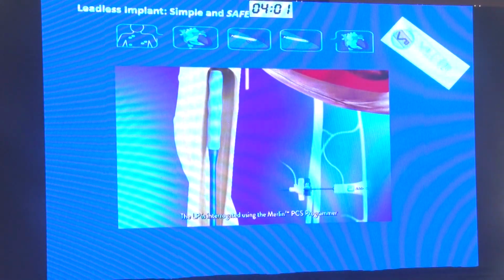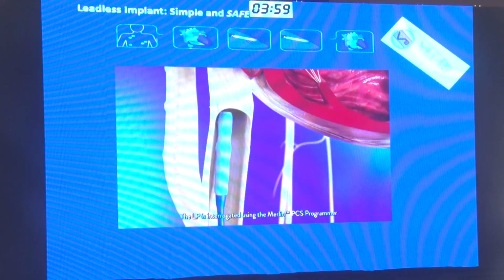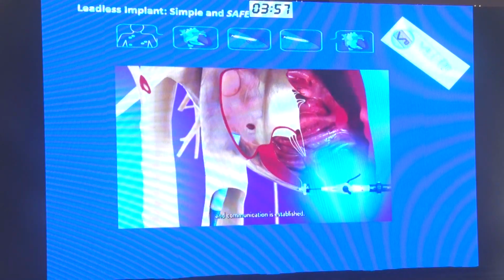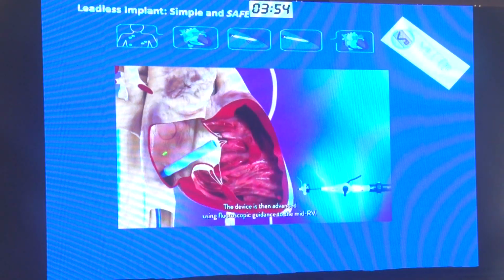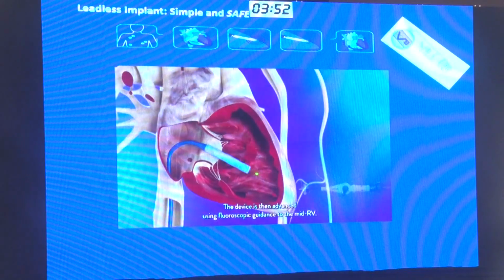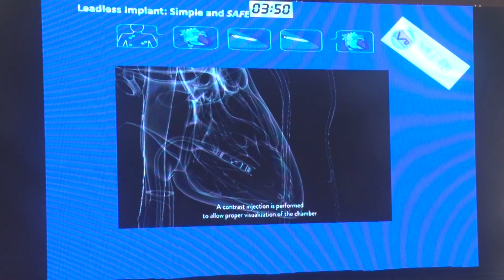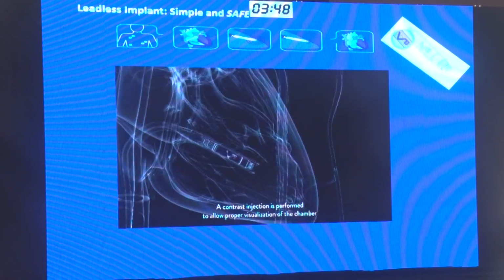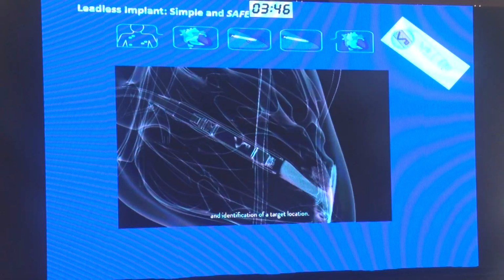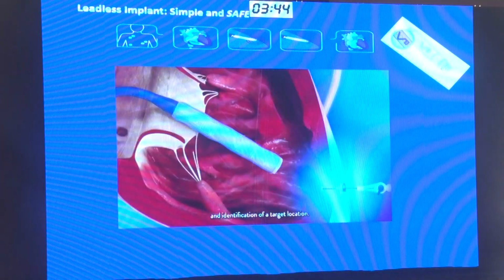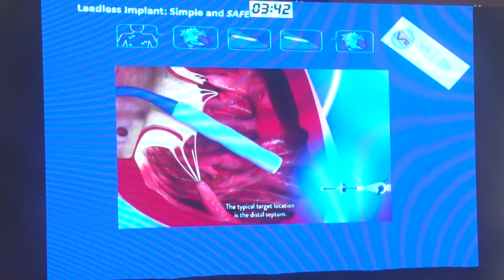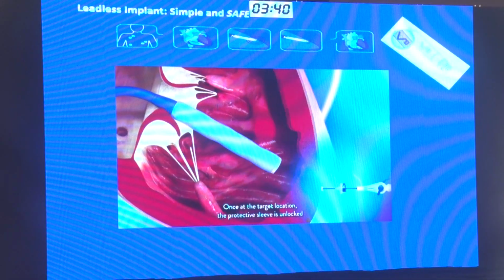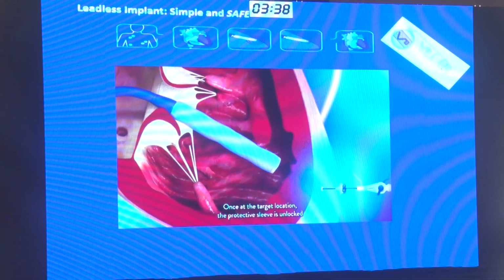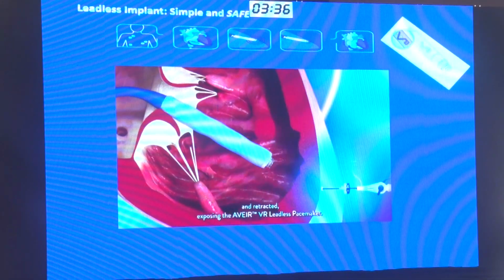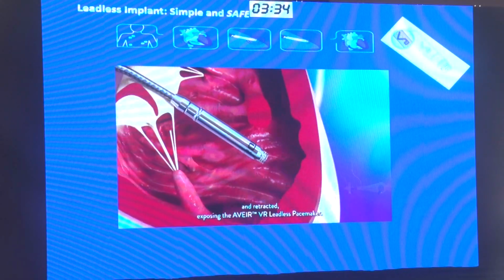The LP is interrogated using the Merlin PCS programmer, and communication is established. The device is then advanced. This is the right atrium, it goes into the right ventricle. A contrast injection is performed to allow proper visualization of the chamber and identification of a target location. The typical target location is the distal septum. Once at the target location, the protective sleeve is unlocked and retracted, exposing the AVEIR VR leadless pacemaker.